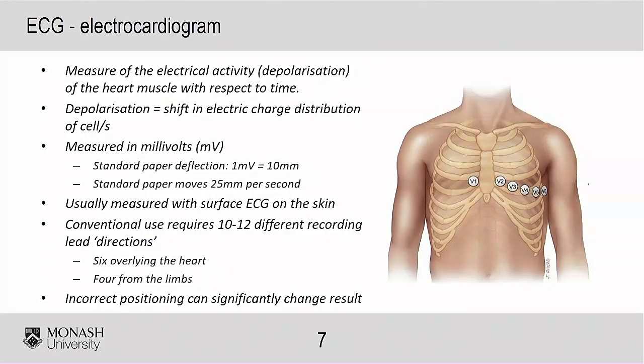It conventionally uses between 10 and 12 electrodes. Only actually needs 10, but it's typically called 12-lead ECG as well. And by the way, ECG also means EKG. They're exactly the same thing. But related to these sensors, you have to place them along the chest. So you have 6 overlying the heart, and then you have 4 from the limbs. So you have 1 on each hand and 1 on each leg as well. The incorrect positioning of these sensors can obviously significantly change the result that you're going to get.